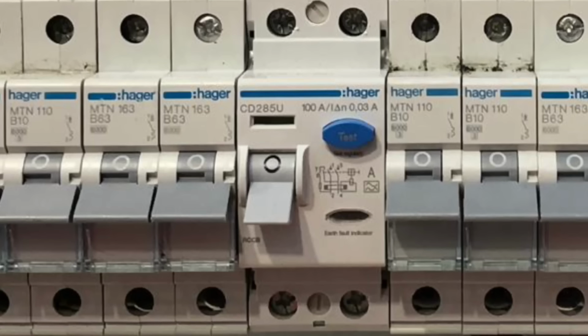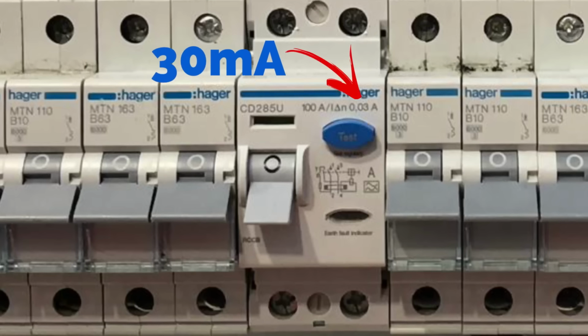In the 18th edition, it told us to make a consideration for overload protection of this type of device as well. This is the only type of device we use today that won't trip if it has overcurrent going through it. So what we have to do is either consider how many amps could be run from the RCD, in which case these wouldn't add up to more than the RCD. Right. Or what we've done at Hager is actually default to the maximum current for the consumer assembly of 100 amps. So notice also 100 amp type. Right. So it's a 100 amp RCD. So you can never draw more current through here than we can connect up to the board anyway. To the main board. Brilliant.